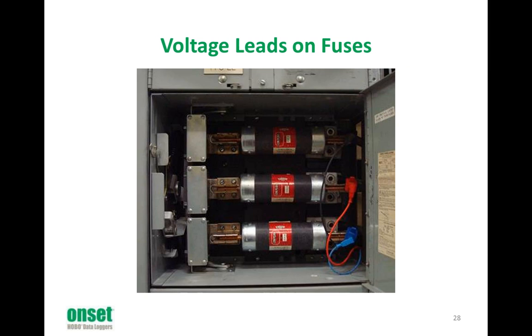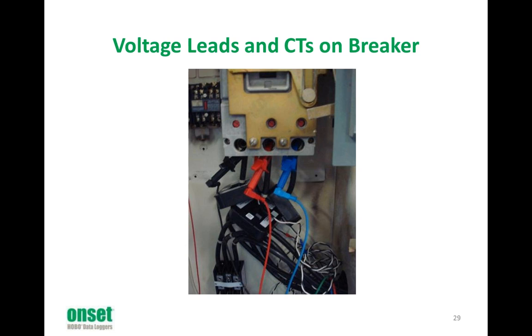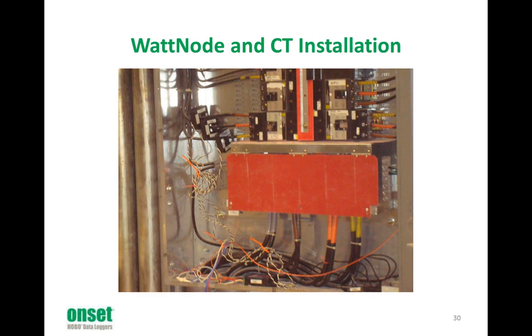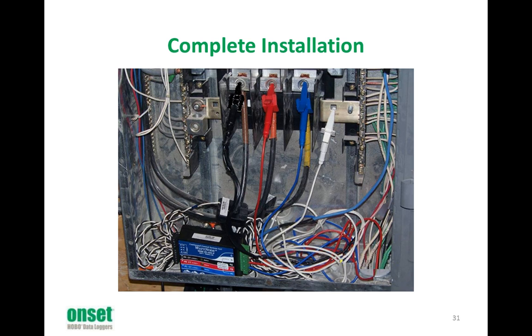Here's voltage leads on fuses inside a main switchboard or a motor control center. And here's voltage leads and CTs on a breaker. And here's a Wattnode and CTs in a 480 volt electrical panel. And then here's a complete installation in a smaller commercial electrical panel. We have our voltage leads at the top, followed by our CTs. Our Wattnode is located at the bottom, and the wire would run out of the panel to the data logger.